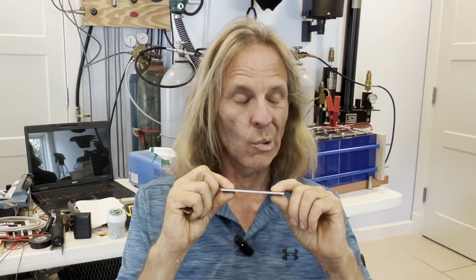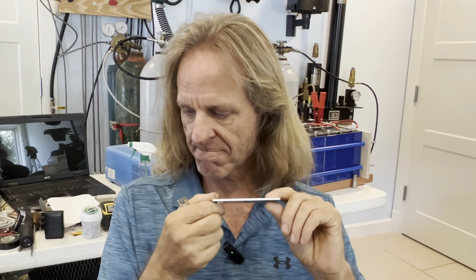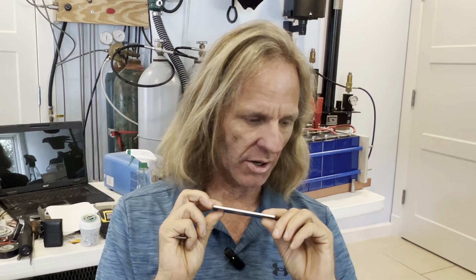Is it enough to over time loosen up those terminals? We've had that problem in the past with electrical wire and terminals that use aluminum, and you actually have to go back and tighten them up over time, because they'll loosen up in your electrical panel. So I don't want to use aluminum bus bars, even though I have aluminum terminals on the batteries.